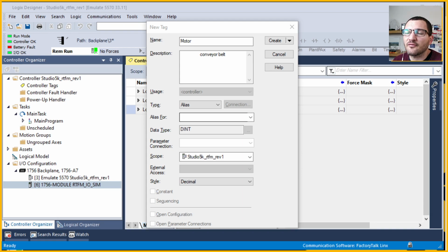So normally it's good practice when you are programming new code to configure your tag to map across to an internal memory. So your physical input is mapping to a memory, and then you use this memory throughout your program, so you don't have to change it. And there are various reasons to do that, right? For housekeeping, which I'm going to cover in the near future.